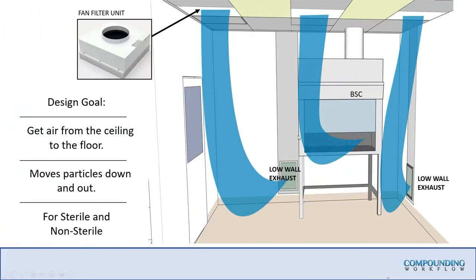The design goal called out in USP 797 — also applicable to USP 800 — is to move air from the ceiling to the floor to ensure good room dilution. USP 797 references low wall returns, or low wall grilles, and in a hazardous drug room these become low wall exhaust because air is exhausted out of the building, as is the biological safety cabinet.